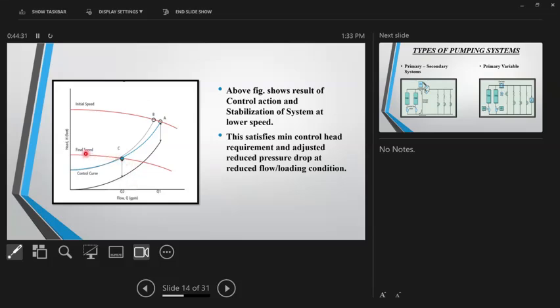So the final system curve, or the final speed, I should not call it a system curve. Final speed is where you are satisfying your flow requirement, and the control head is honored. So that's how the control system selects the speed.